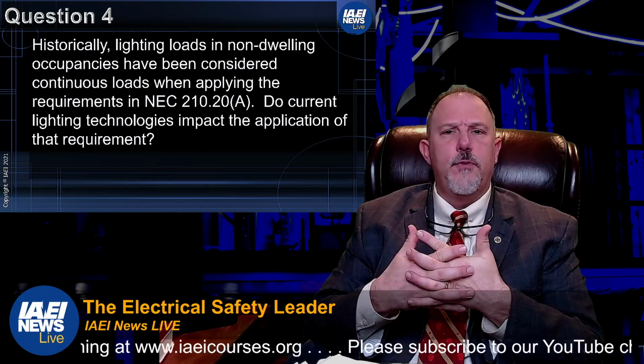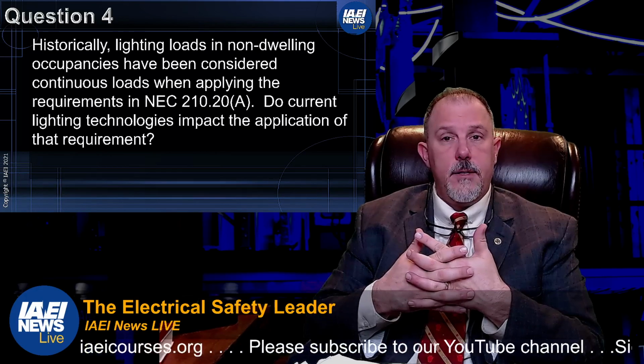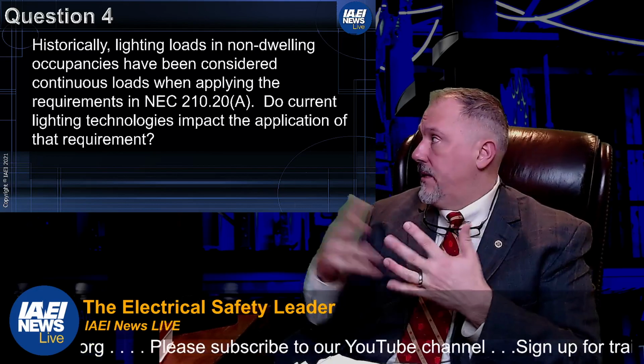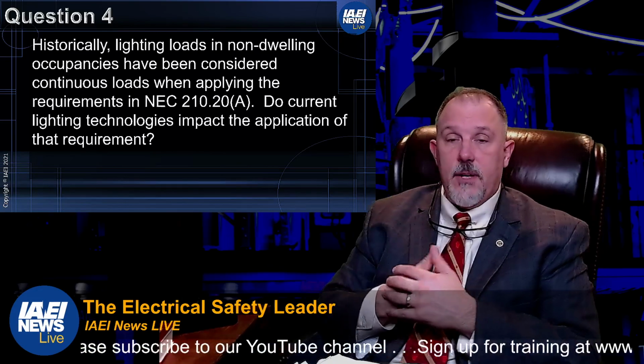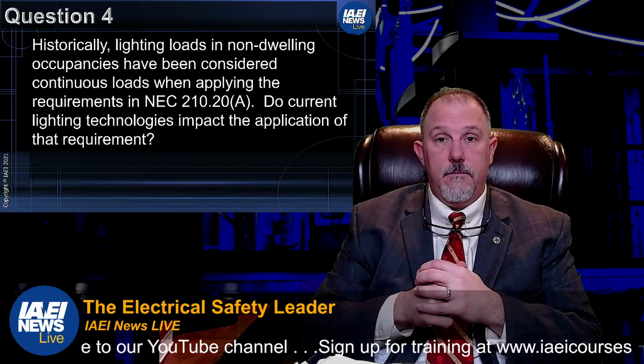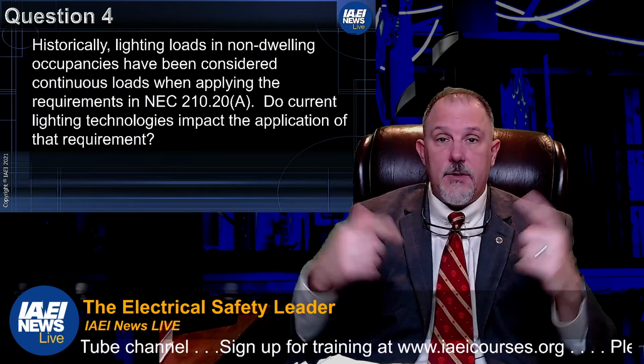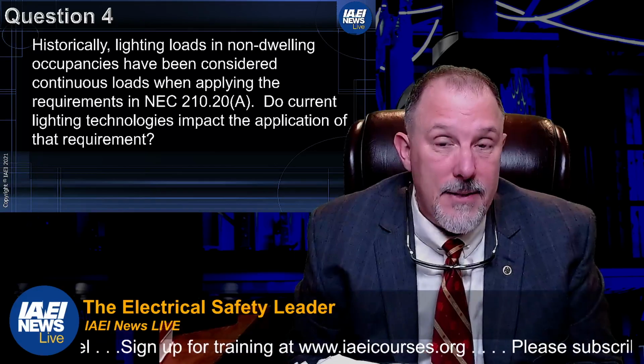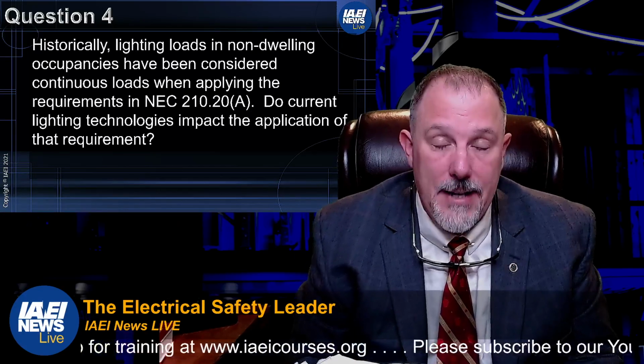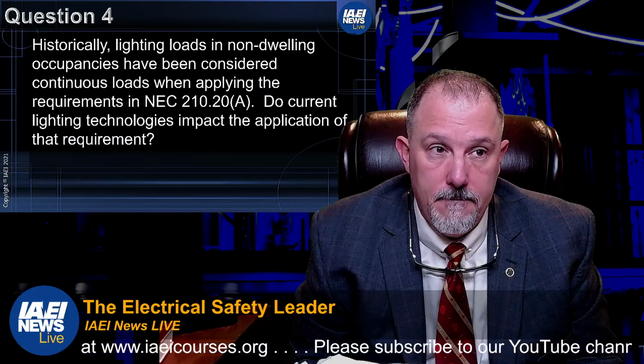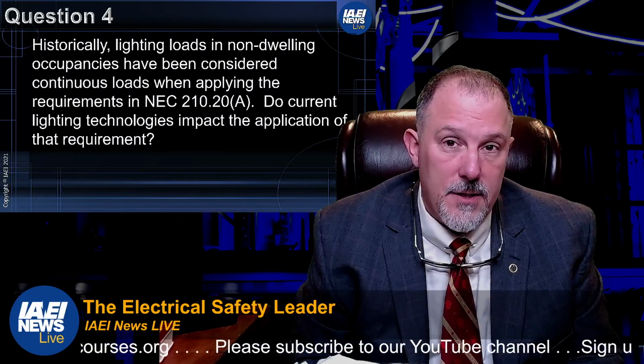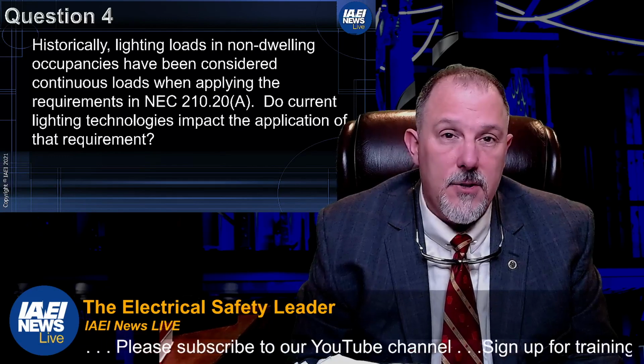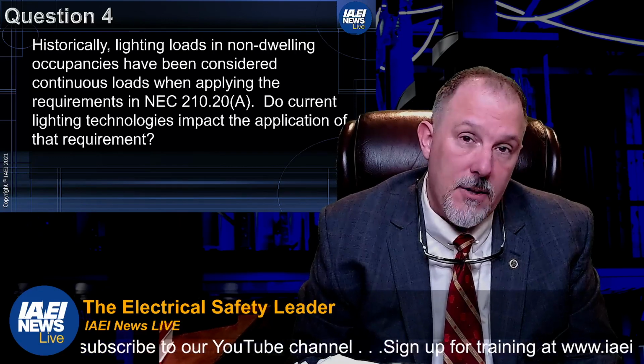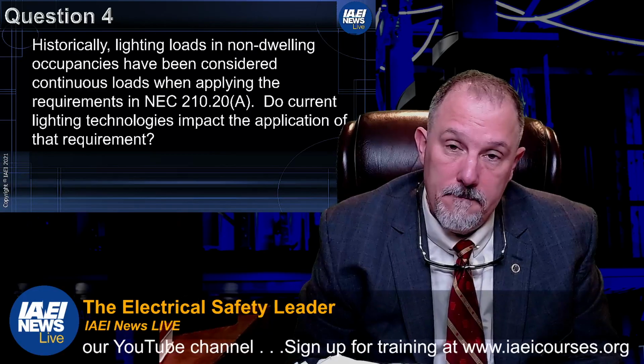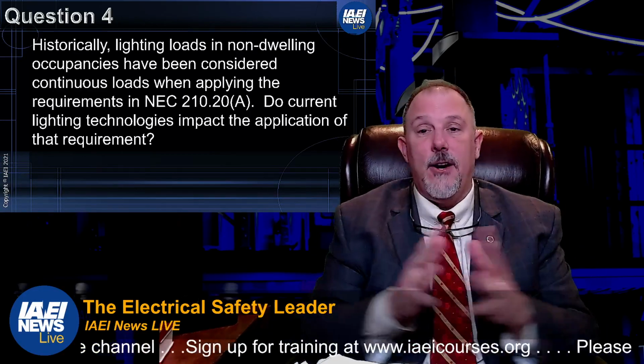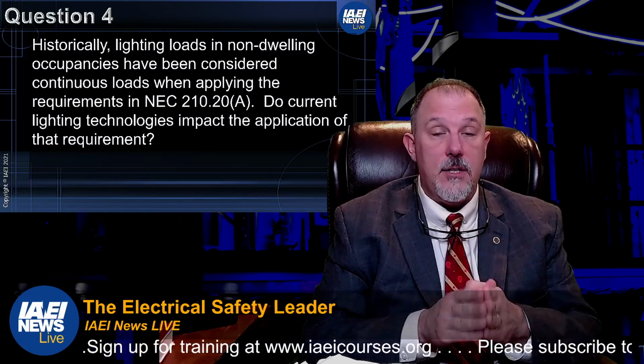I don't know how I would prove that, honestly. When I look at the lights, my basement lights have been on all day because I'm in the basement. My upstairs lights have not been on all day, but they will be on all night, and my basement lights will be off because I'm not going to be down here tonight. In commercial applications, can you truly say an office is not going to have the lights on during the day, and they're not continuous loads, 3 hours or more? Lighting is a hard sell when you say it's not going to be continuous, in my opinion.